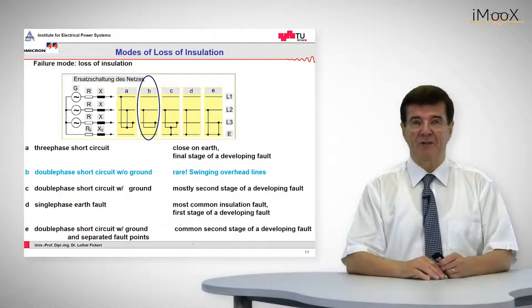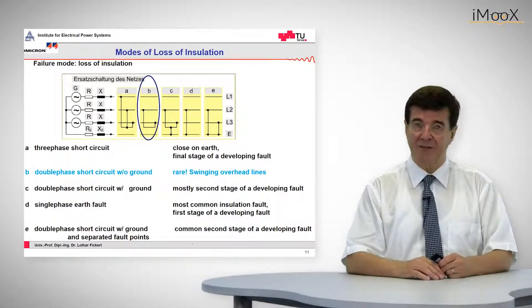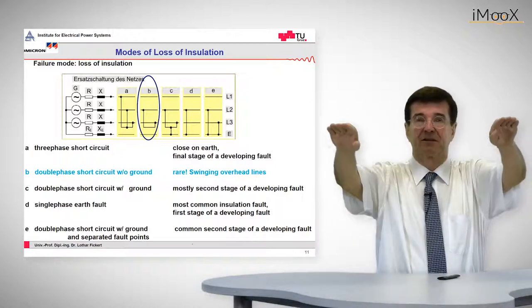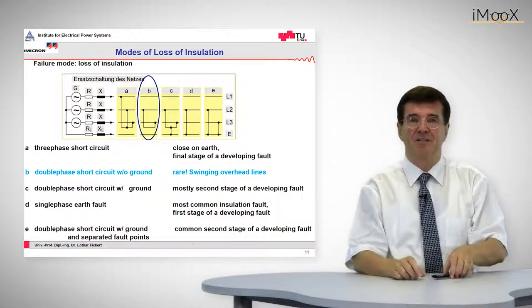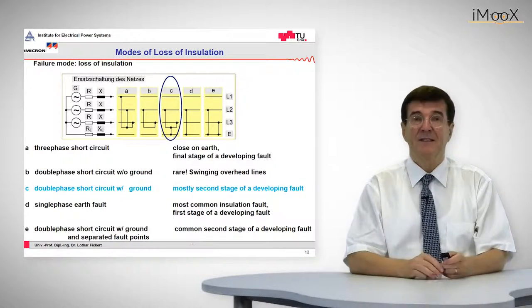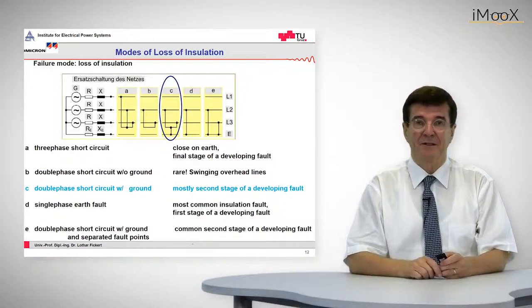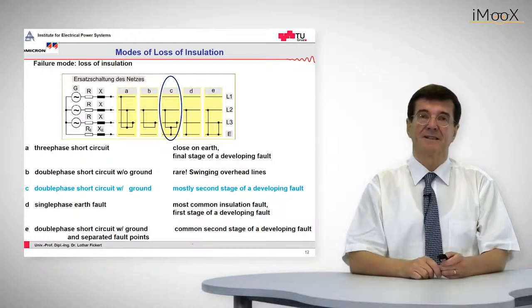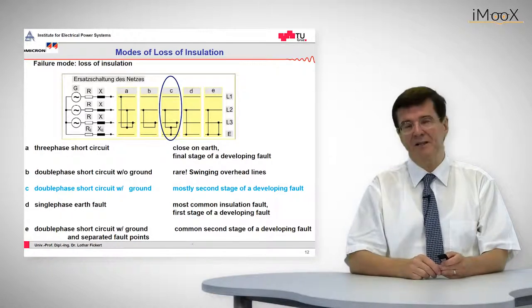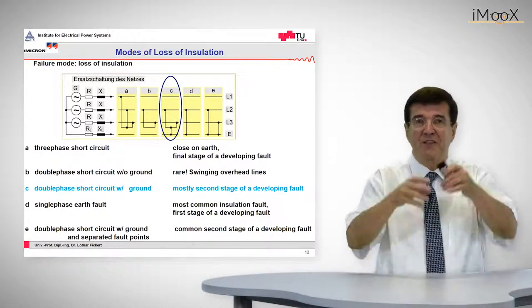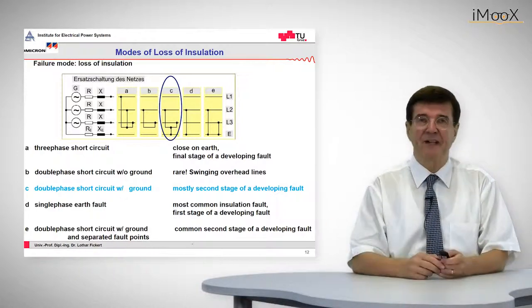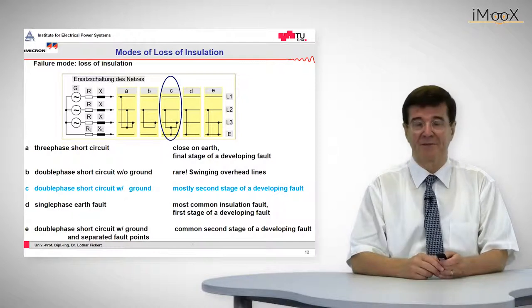The next one, the double-phase fault without ground, is quite rare. It only occurs in overhead lines where two phase conductors may touch each other by their swinging in the air. More common is fault type C, which is the double-phase short circuit with ground. This regularly starts with a single-phase to ground fault which, by the effect of the burning arc, afflicts the next phase so that we end up with a double-phase to ground fault.